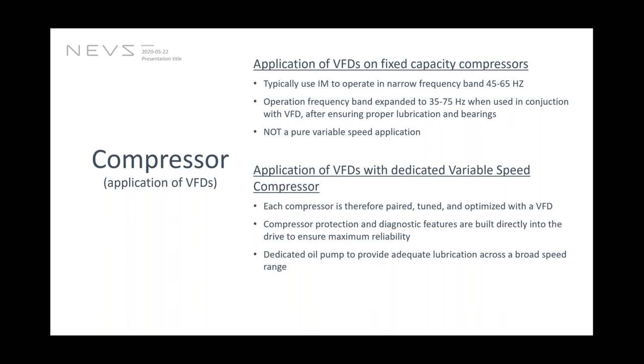Now, another type is a dedicated variable speed compressor with VFDs implemented. Each compressor in this type of application is tuned and optimized with the VFD. Compressor protection, especially with respect to pressure buildup and overheating, and diagnostic features are built directly into the drive to ensure reliability. One important thing to mention here is that compressors are usually optimized to operate in a certain very narrow band, mainly due to bearings and lubrication. So this type of variable speed compressor has a dedicated lubrication system, might be with the use of some oil pumps as well, so that it has proper lubrication for a broad speed range.